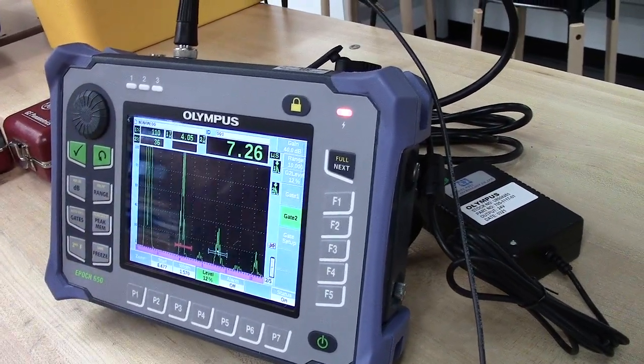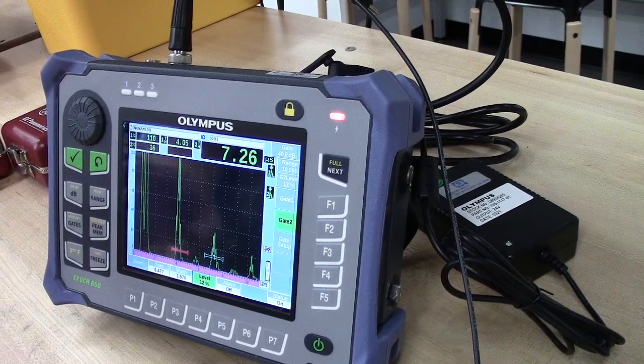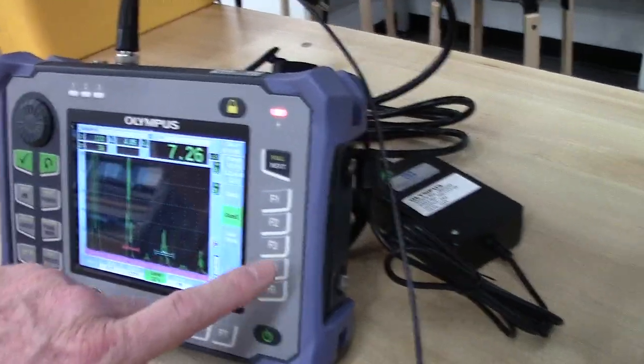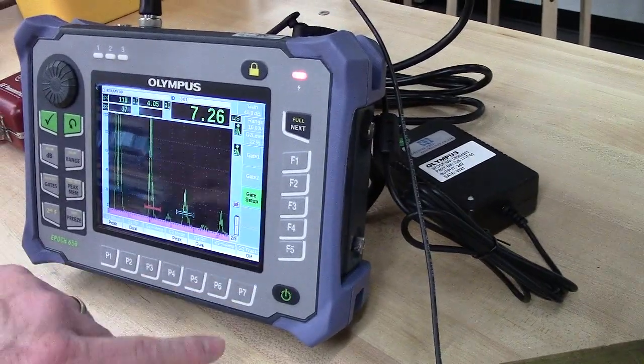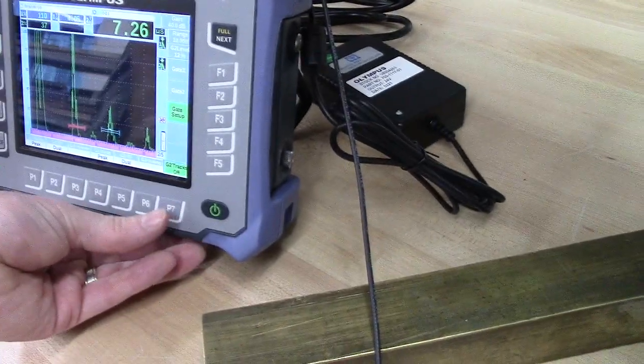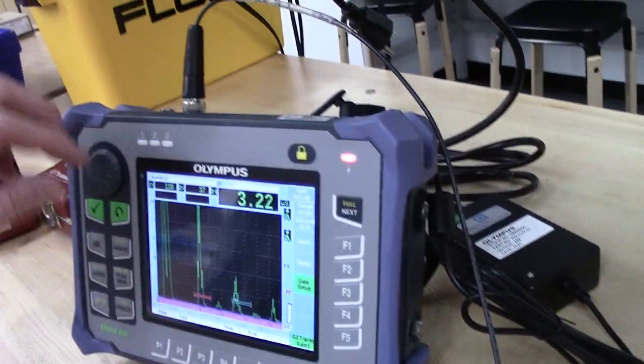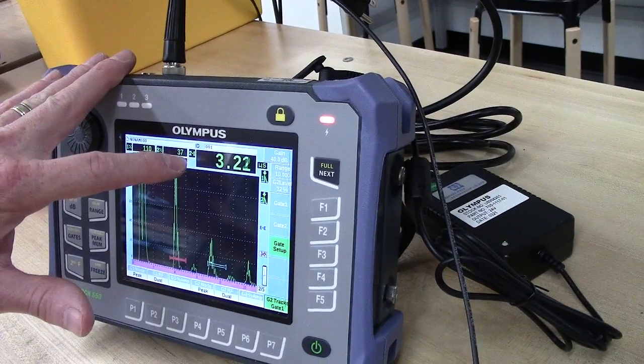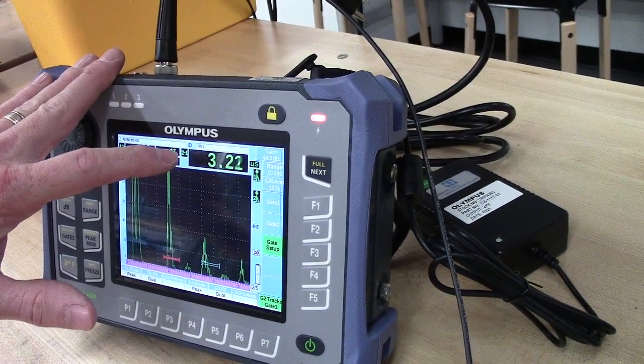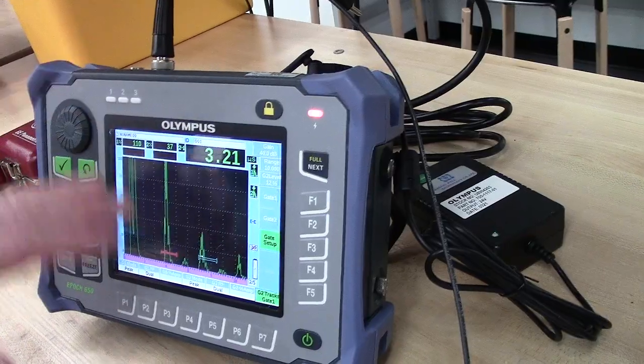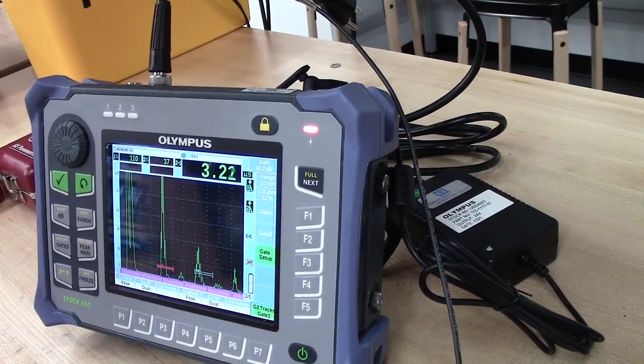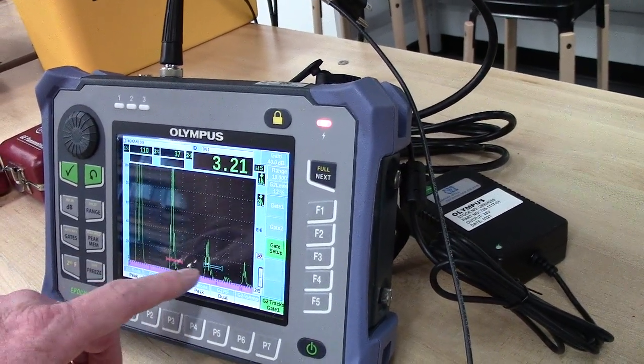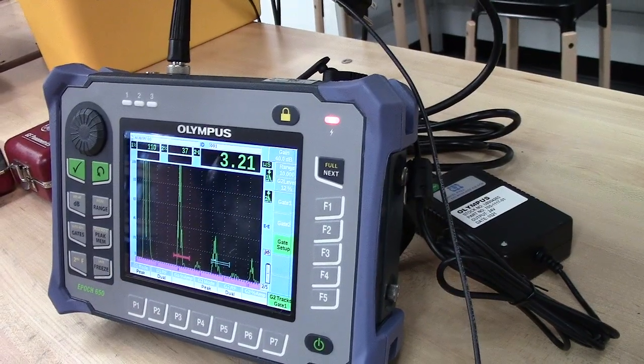So to switch to that, gate setup. That's what we want. So gate setup, and then G2 tracks. Down here, switch this to on. So now it's picking the difference between the peak. So it's subtracting the peak of 1 from the peak of 2. And we're getting the 3.2 microseconds. And that matches our scale down here for what we want. And I know that that should be fairly close to giving us the right speed based on the thickness here.